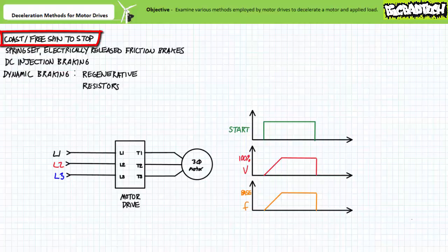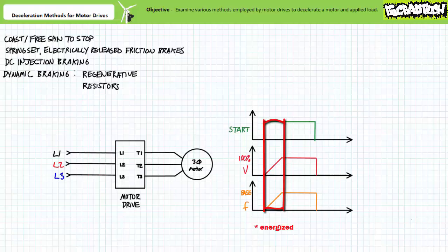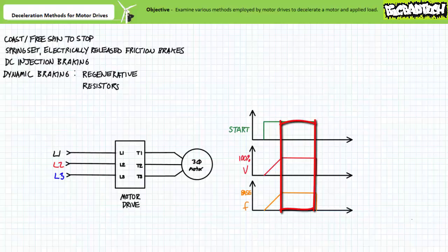Perhaps the simplest means a motor drive can utilize to de-energize a running motor is to immediately cease conduction without employing a deceleration period. This would be quasi-equivalent to the opening of an electromechanical contact or breaking connection to the power source. When energized, the motor drive executes a timed acceleration ramp up of applied voltage and excitation frequency. During constant speed mode, applied voltage and excitation frequency remain fixed. When de-energized, the motor drive immediately ceases conduction. The rotating magnetic field produced by the stator immediately collapses and the rotor and applied load coast or free spin to a stop. While suitable for some applications, free spinning to a stop is imprecise and can take a measurable time period for the rotor to come to rest if it has established a degree of rotational inertia.